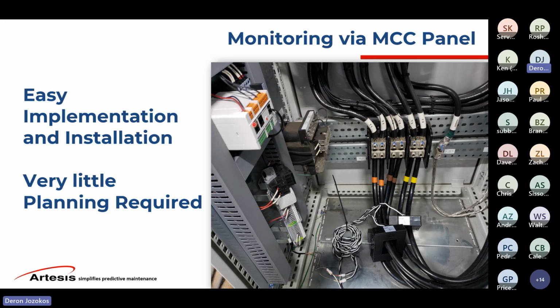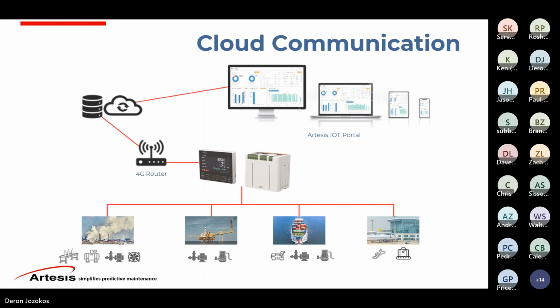And then the Ethernet communication, Cat6 communication out. If you're using the local HMI, which is not required for the system to work, it's just nice to have a local output. That's powered and gives all the information through the port next to it here. So that's another Cat6 cable. From the EMCM, we need to get the data to our server, or your server. We can do that a couple of different ways. To get it onto the cloud, we can go through an LTE cellular modem router. You could have multiple units, say 20 units, going into a switch into the router, get it onto the cloud, and then you just have local dashboard access.